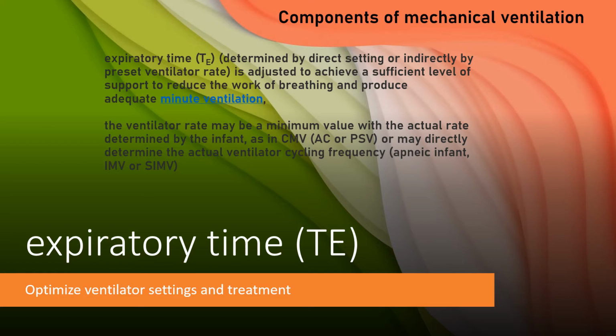Expiratory time is determined by direct setting or indirectly by preset ventilator rate. It is adjusted to achieve a sufficient level of support to reduce the work of breathing and produce adequate minute ventilation. The ventilator rate may be a minimum value with the actual rate determined by the infant, as in CMV or AC or PSV, or may directly determine the actual ventilator cycling frequency, as in an apneic infant, or during IMV or SIMV.